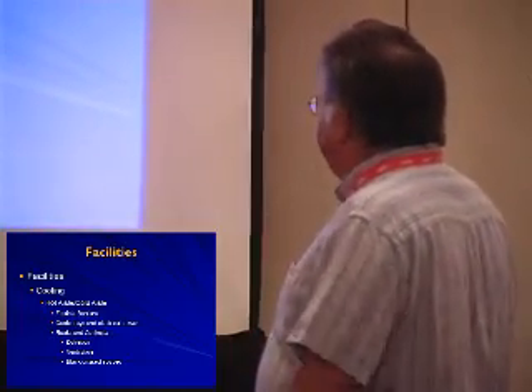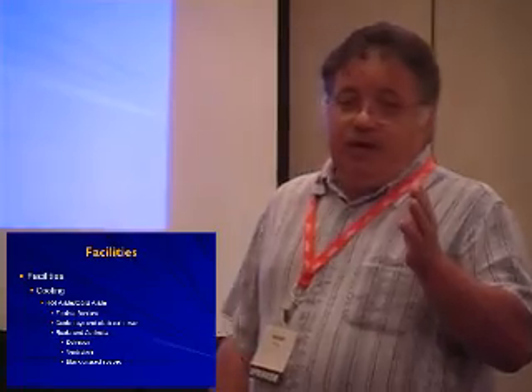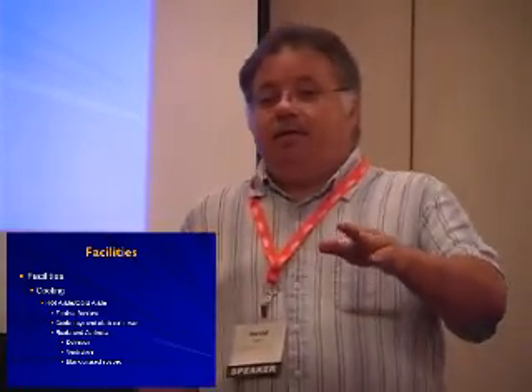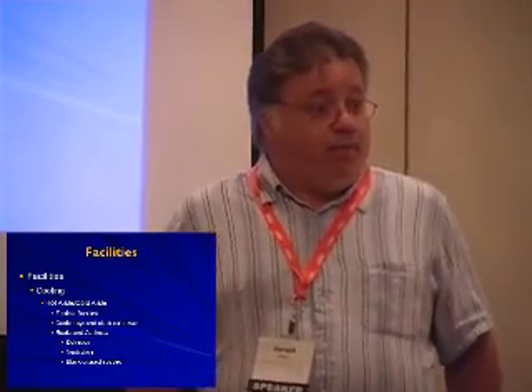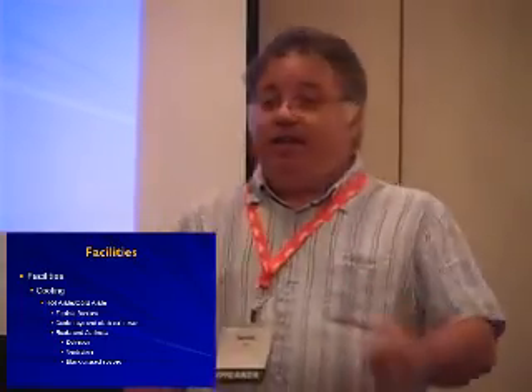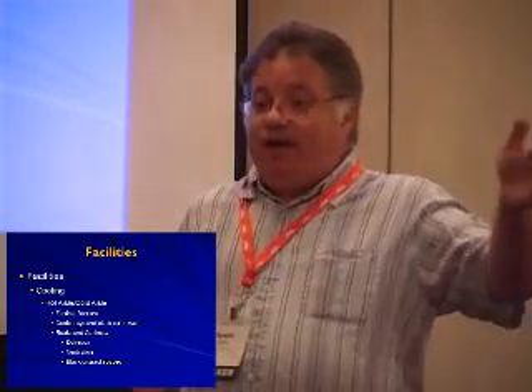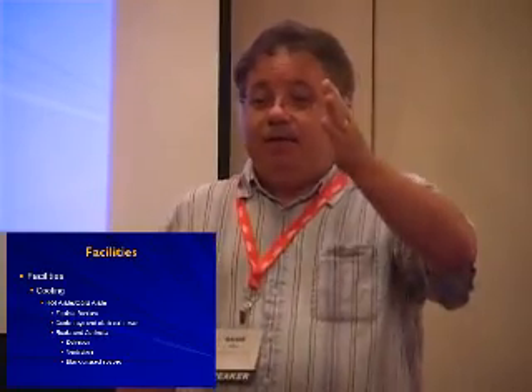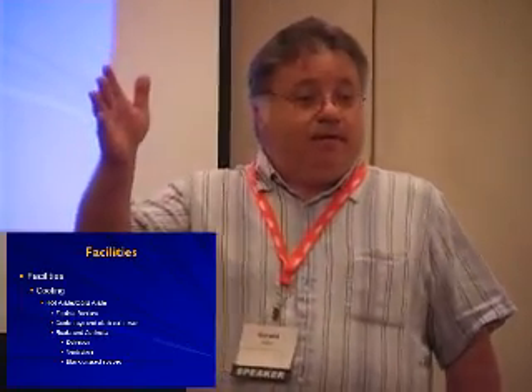So with flexible barriers, cable trays and electrical power: don't put anything underneath the floor. A lot of people argue, well, where do you want me to put it? On top, in the hot aisle. Move the cable tray over so it's in the hot aisle, not the cold aisle, because you don't want anything impeding the flow of cool air. Hot air, you don't care about - it's already warm, what are you going to do, make it hotter?